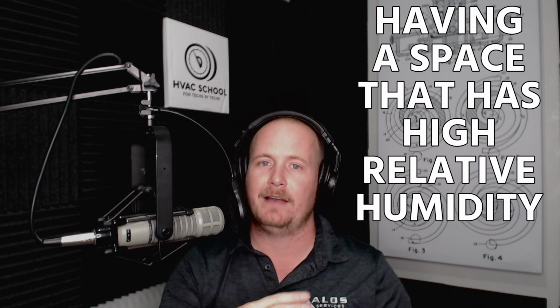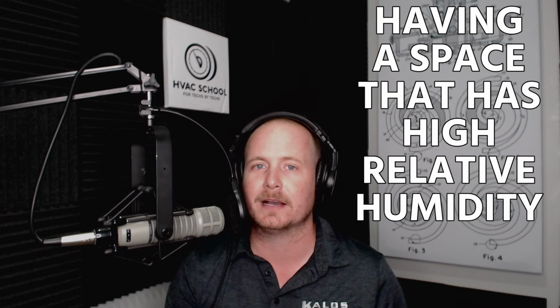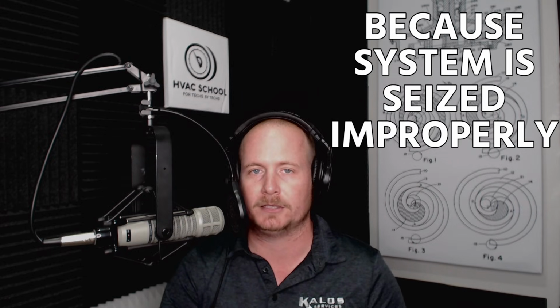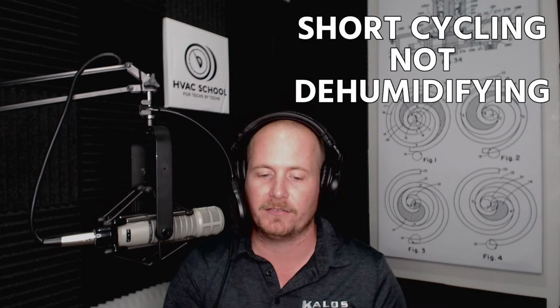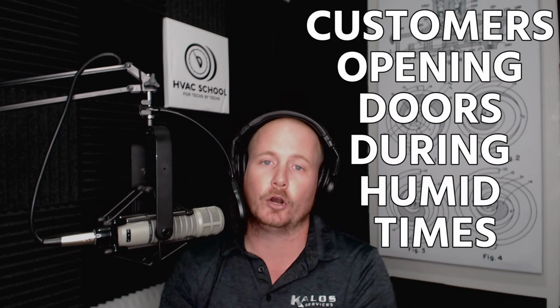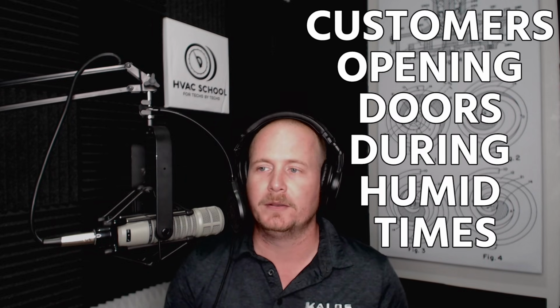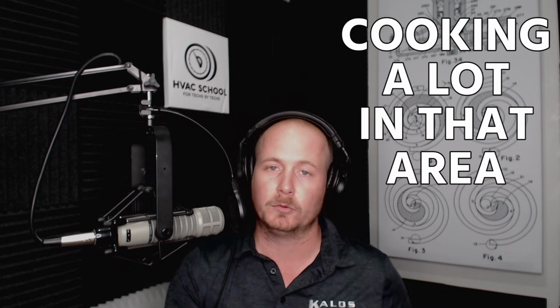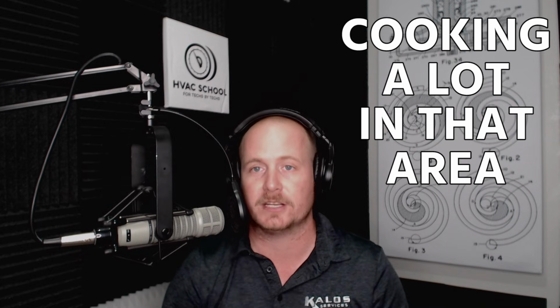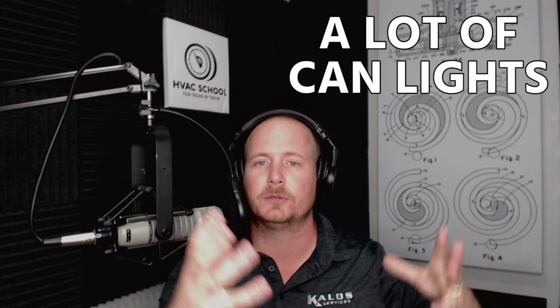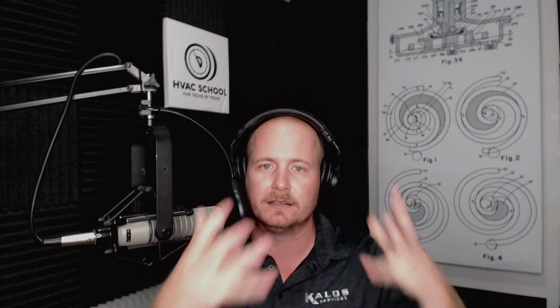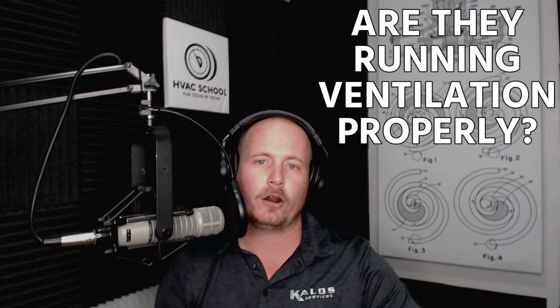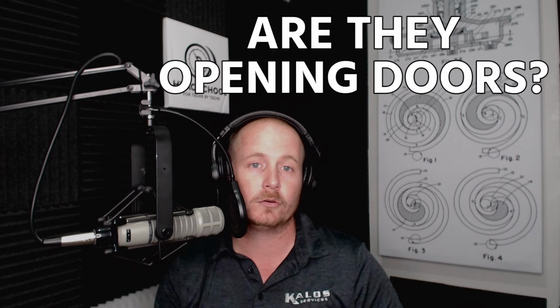So it's things like having a space that has high relative humidity, maybe because overall the system is sized improperly, it's oversized, so it's short cycling and not dehumidifying. Or maybe you have a customer who's opening the doors into the space during humid times, and so a lot of air is getting in that way. Maybe they're cooking a lot in that area, and so there's a lot of moisture from there that's not being ventilated with a proper kitchen exhaust, or maybe it's being recirculated into the space. Or maybe they have something like a lot of can lights going into an unconditioned attic where that moist humid air is infiltrating into the space due to air leakiness. So you want to look at air leakage. You want to look at, are they running ventilation properly? Are they opening doors? All those sorts of things.